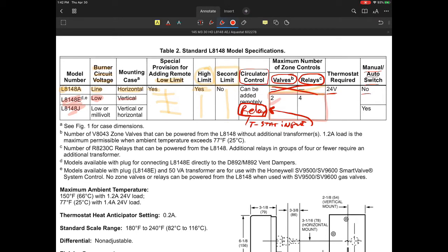Over on this side, they're telling me that both of those two lower models on the bottom here, the E and the J model, allow you to control up to 2 zone controls, which they list as item B. Item B is a number of V8043 zone valves, like your Honeywell zone valve, and they're saying we can power up to 2 of those valves. Any more than that, you will not be able to do without adding additional transformers. I would not recommend adding any zone valves beyond 2 in those cases.